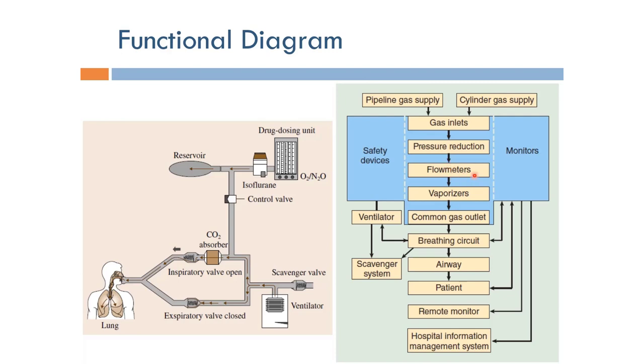The gases then go through a flow meter and vaporizer. The flow meter controls the mixing of oxygen and nitrous oxide, and the vaporizer is the device responsible for adding the inhalation anesthetics.